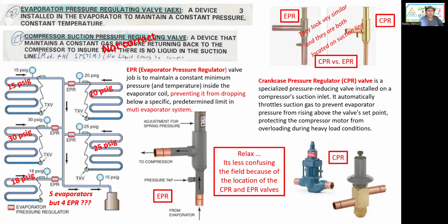That's the evaporator pressure regulator, not the crankcase one. Now, CPR and EPR look very similar. They're both located on the suction line, but one is close to the compressor and one is close to the evaporator. Relax, it's less confusing in the field because of the location of the CPR and the EPR. Okay, I'm sorry, I said it the other way around: EPR is for multi-evaporator systems, CPR is for freezers.